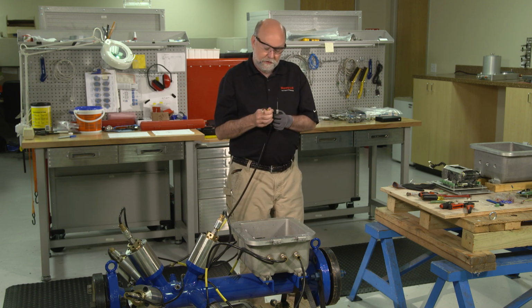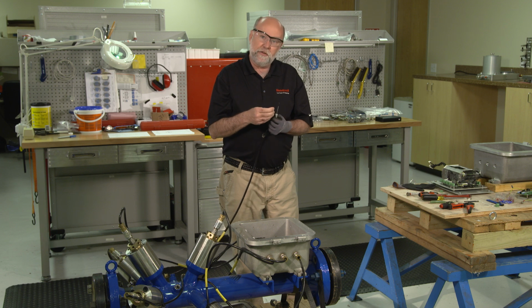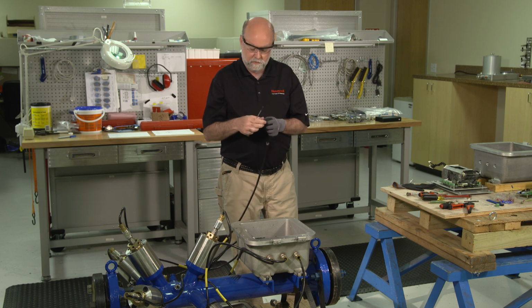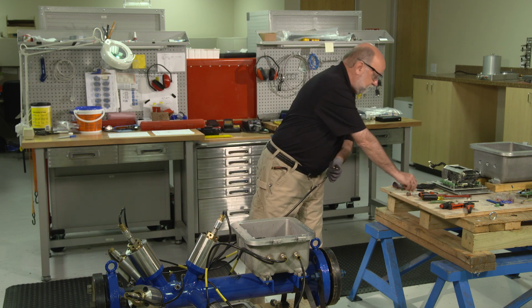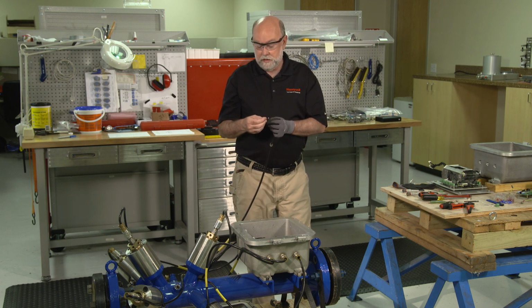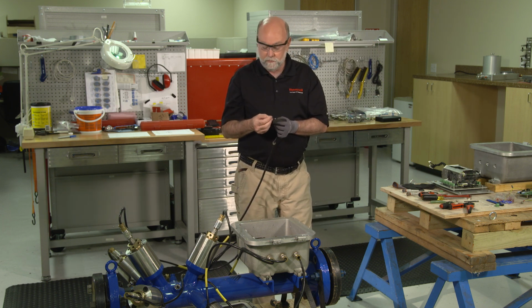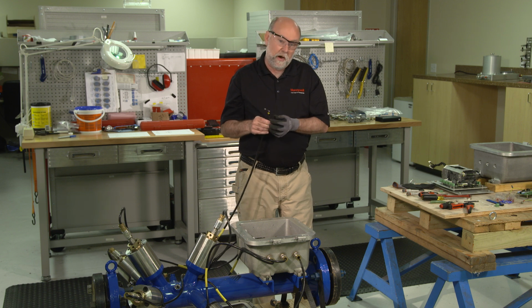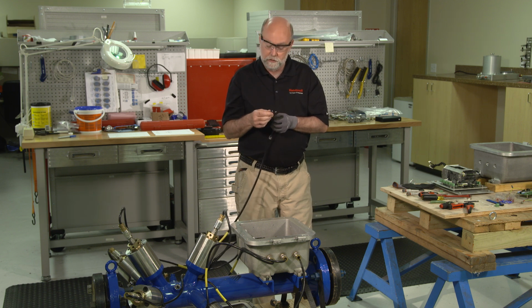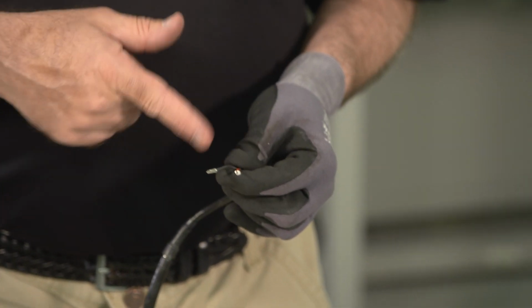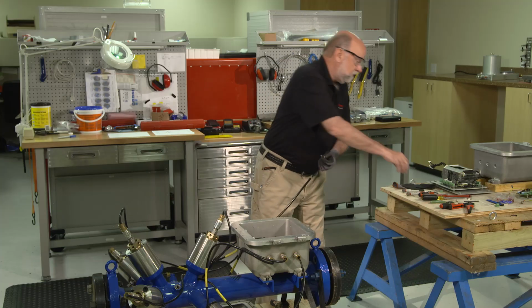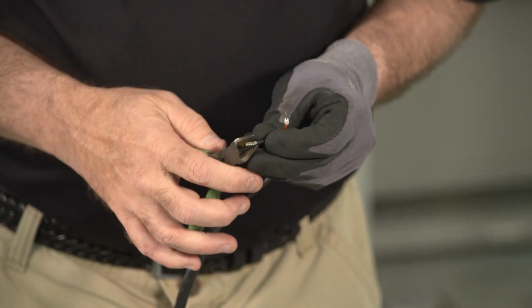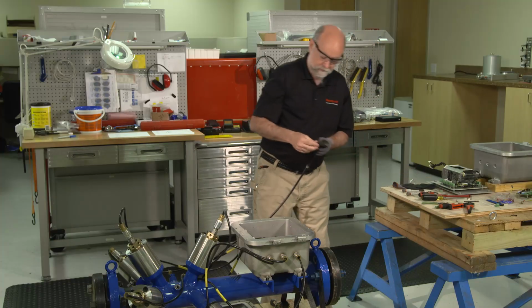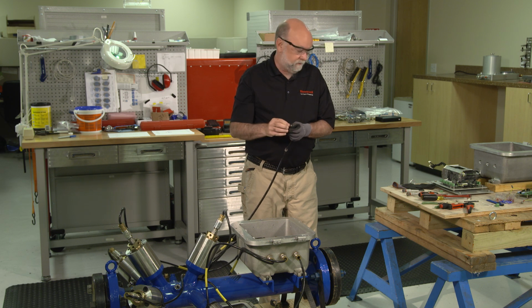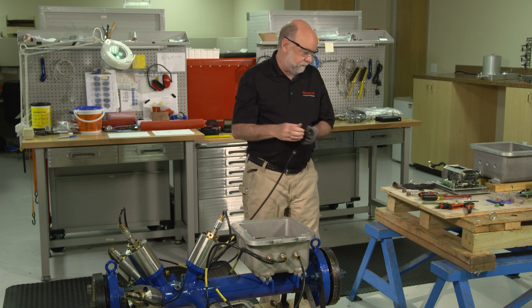What we're going to do with these transducer cables, the current system uses a 2-wire excitation and signal processing method. There's actually 3 wires inside this cable. There's 2 wires and a shield. What we've done is on the current system, we've taken the shield and connected it to the low side wire. We're going to cut the ferrule right off on the side that has the shield and the negative wire connected.